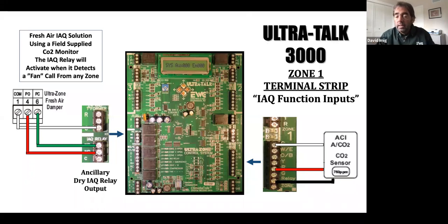There is the IAQ relay on this zone terminal as well. Here I'm using a third-party CO2 sensor to activate my fresh air damper. And keep in mind, I must see a fan call for that to happen from one of the thermostats. I cannot energize a fan call with a third-party non-communicating control, excuse me.